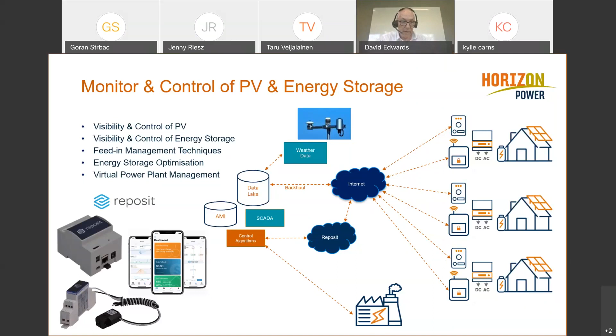So in this visualization, you can see it should start moving in a sec here. This is the same PV systems that we're monitoring, but this time we're looking at voltage on a cloudless sunny day. The bars are green when the voltage is below 254 volts, and they turn red when it's over 254 volts. And the distribution graph from our research partners at Murdoch on the right-hand side shows the number of over-voltage events that were detected using the WattWatcher data.